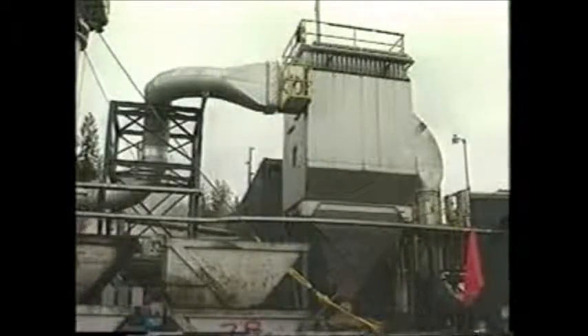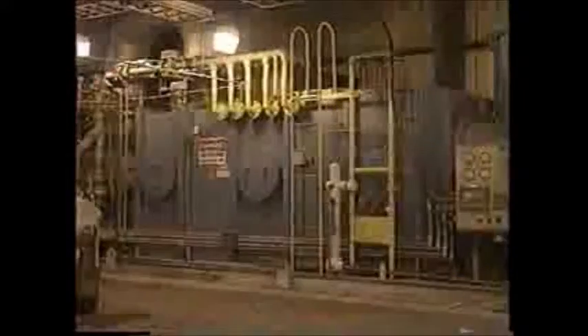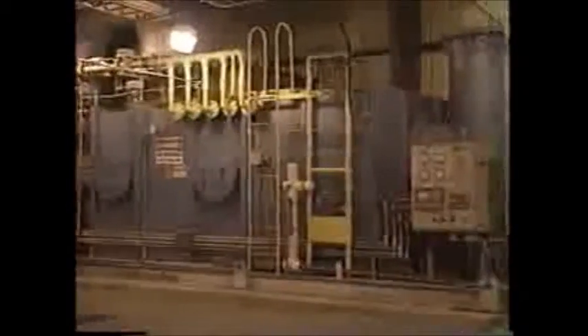gas stream. Flue gases exiting the baghouse may contain small amounts of inorganics in the form of acids. These acids are neutralized by the system's scrubber by passing through a spray of sodium hydroxide. As with all the cooling and cleansing water used by the system, the water and sodium hydroxide solution used in the scrubber is treated and recycled on site or is discharged following verification that treatment standards have been satisfied.